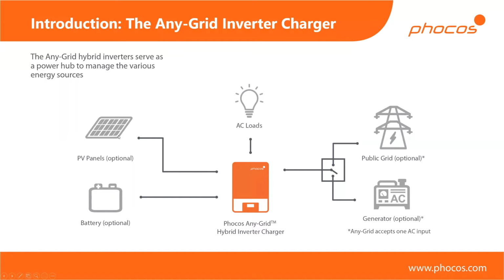Then we have the PV input, which is optional. We have the battery connection, so you can, but you don't have to connect a battery. So this is already a big difference between the AnyGrid and a lot of other devices out there. And then we have one AC input where you can connect either a public grid, or you could connect an AC generator of some kind, a fuel cell, etc. What's important to know here is that we have one AC input. So if you do want to use more than one AC source, you can, but you need to have an external source selector.